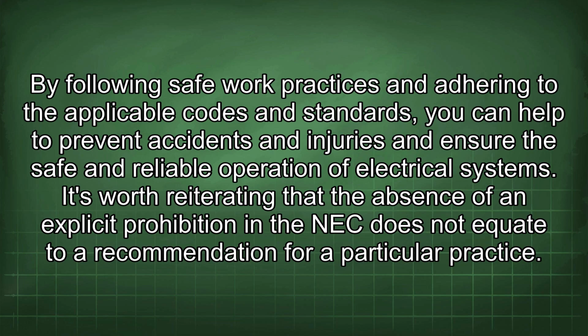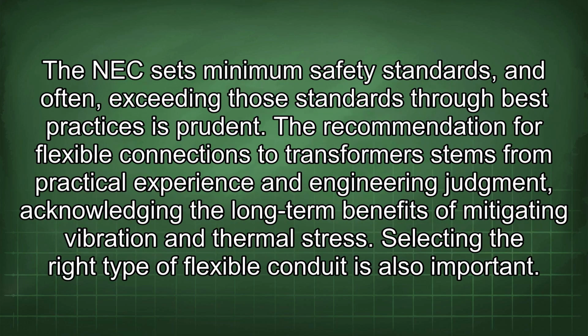It's worth reiterating that the absence of an explicit prohibition in the NEC does not equate to a recommendation for a particular practice. The NEC sets minimum safety standards, and often, exceeding those standards through best practices is prudent. The recommendation for flexible connections to transformers stems from practical experience and engineering judgment, acknowledging the long-term benefits of mitigating vibration and thermal stress. Selecting the right type of flexible conduit is also important.